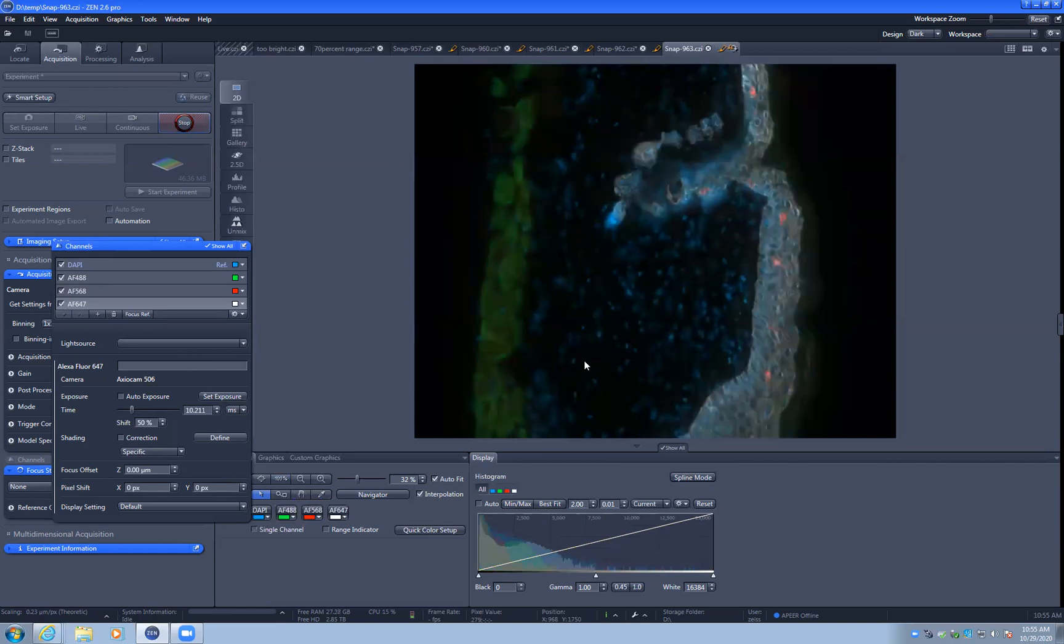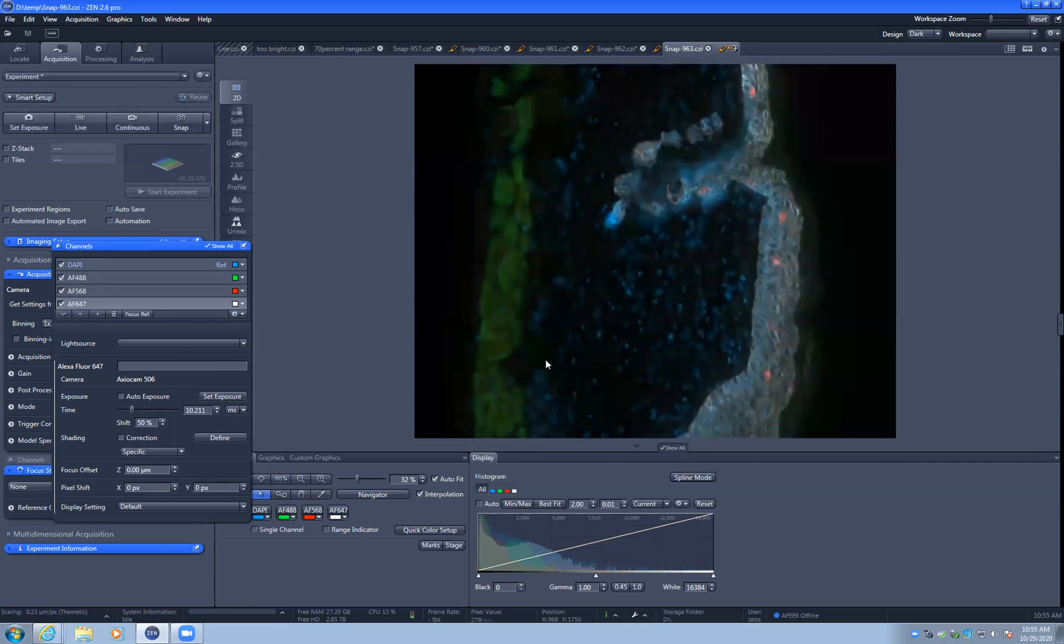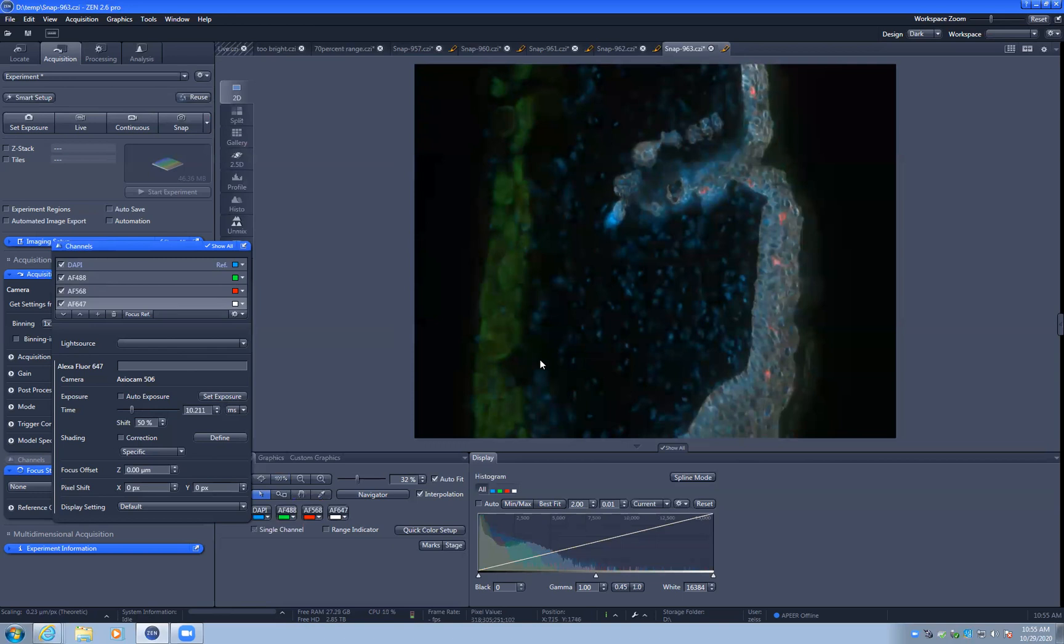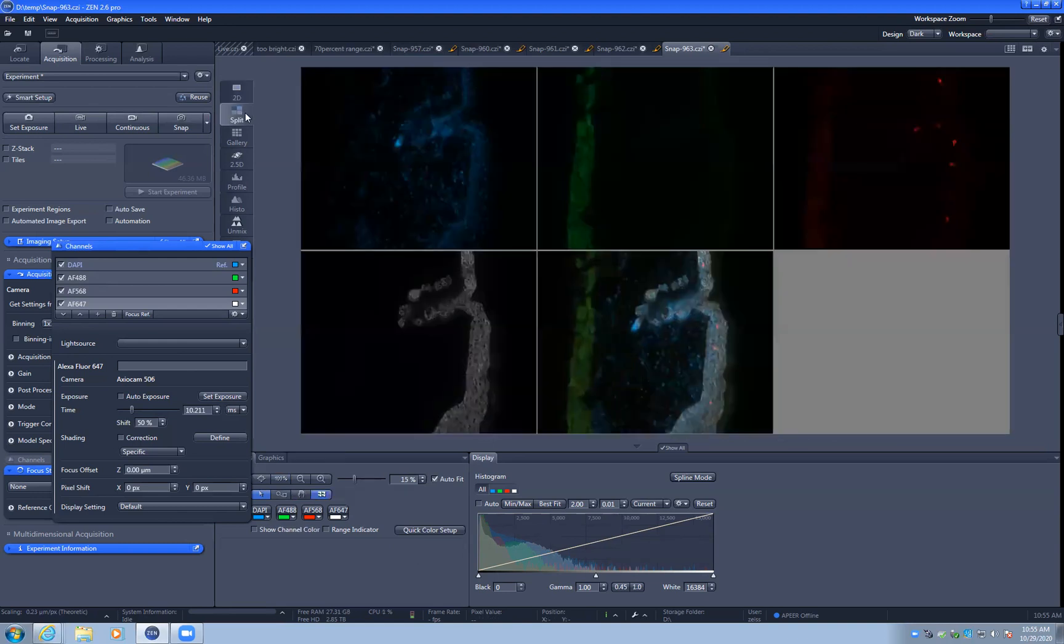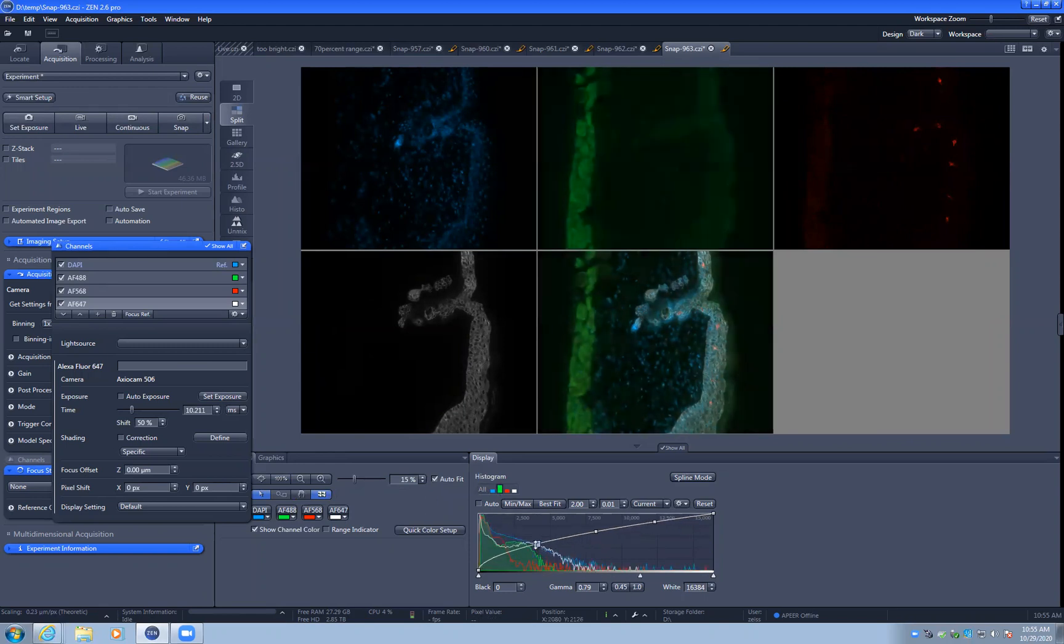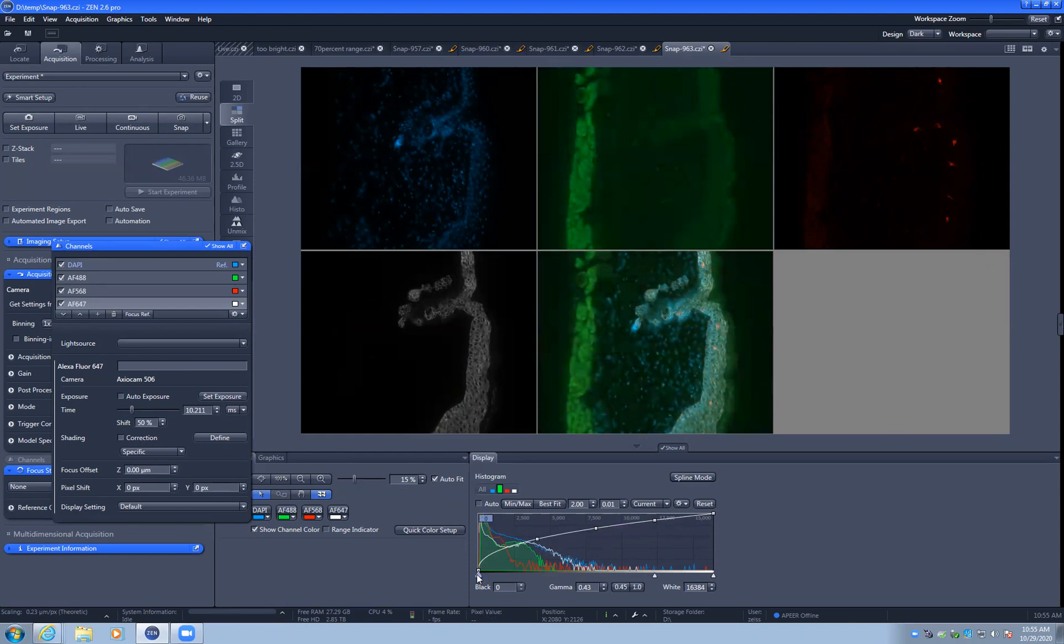And I'm going to do it for the AF647. I'm not even going to look at the image. I'm just going to say auto-exposure at 50% range, set exposure. And now, if we take all the channels, we have DAPI, green, red, and far red checked. It takes a picture where everything is within that range. We can split screen. We can clearly see everything's fine. We can also go into an individual channel. You can see, for display, later, we can do this. We just have to set our methods to show bright areas and green labeled areas in the same image.